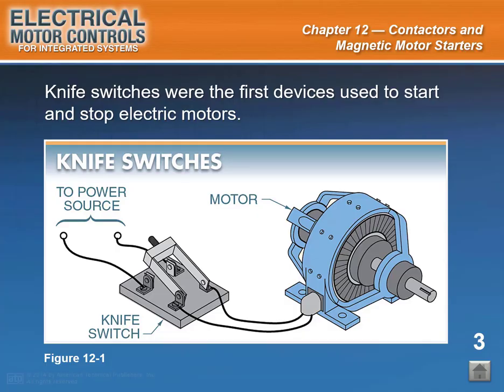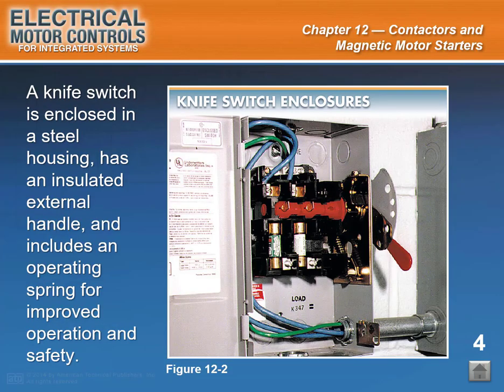Second, the speed of opening and closing contacts was determined by the operator. Considerable arcing and pitting of the contacts led to rapid wear if the operator did not open or close the switch quickly. Finally, most knife switches were made of soft copper, which required replacement after repeated arcing, heat generation, and mechanical fatigue. End of Slide 3. Start of Slide 4.